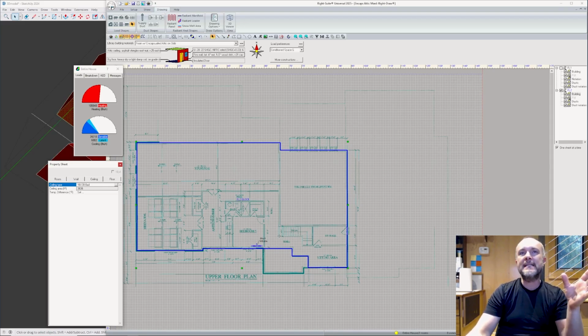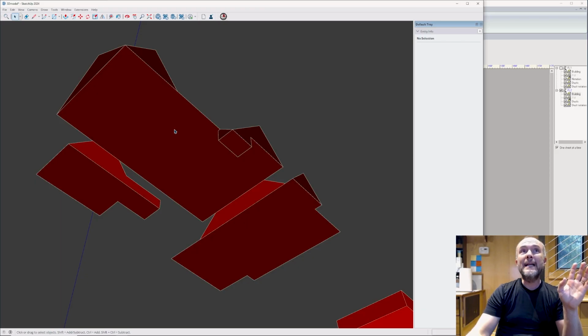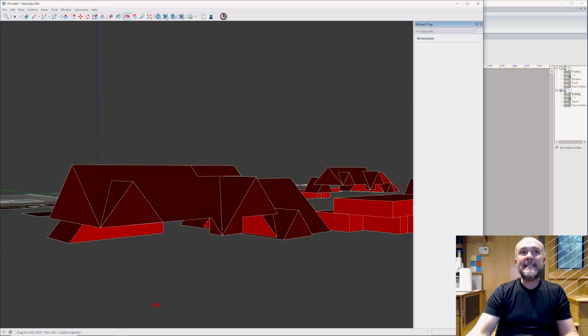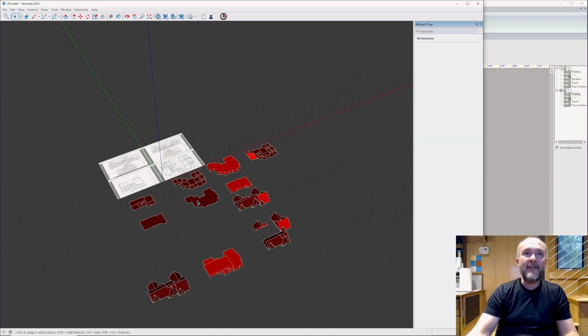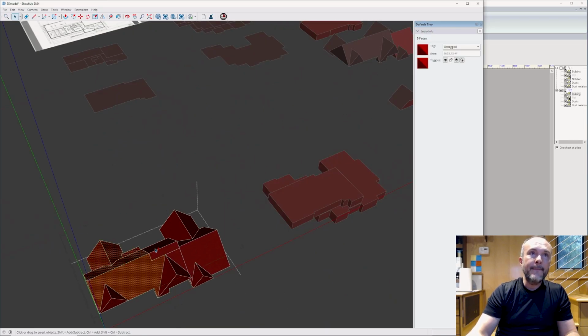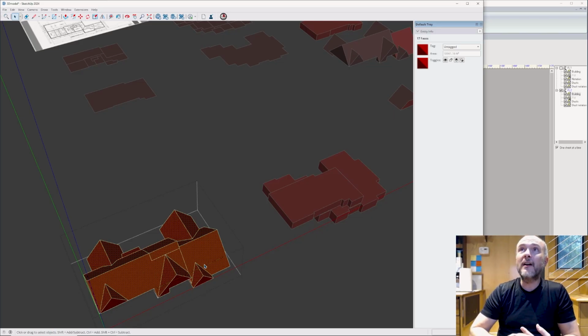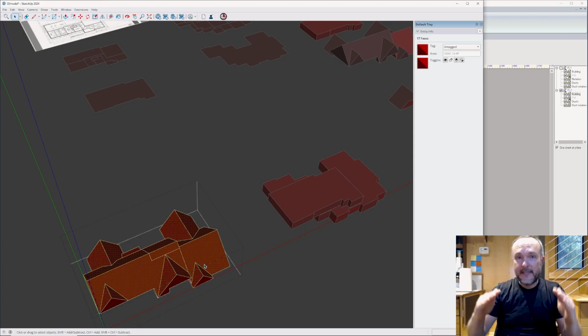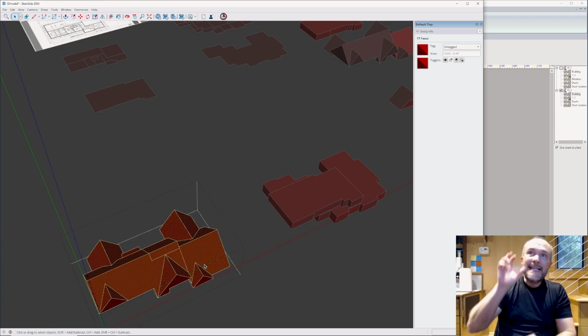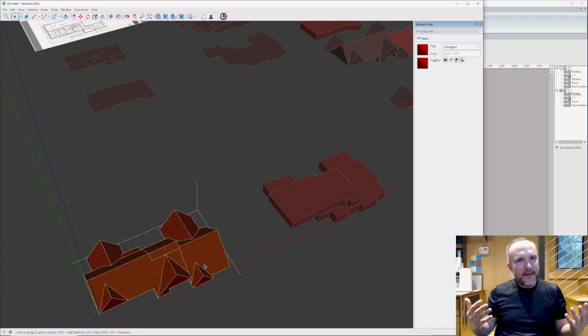So around 3,600, 3,700 square feet of roof surface area. But really, what we've got here is, instead of the total of 7,500-ish, you can see that we've got 10,961. So we have an extra almost 50% of surface area. And since that's not an input in Wrightsoft, it makes me a little nervous. Like, how are they calculating this?